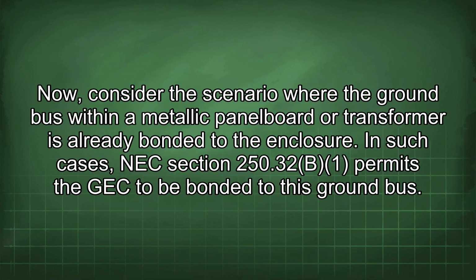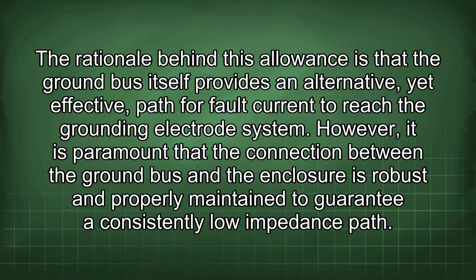Now consider the scenario where the ground bus within a metallic panel board or transformer is already bonded to the enclosure. In such cases, NEC section 250.32 permits the GEC to be bonded to this ground bus. The rationale behind this allowance is that the ground bus itself provides an alternative, yet effective, path for fault current to reach the grounding electrode system. However, it is paramount that the connection between the ground bus and the enclosure is robust and properly maintained to guarantee a consistently low impedance path.